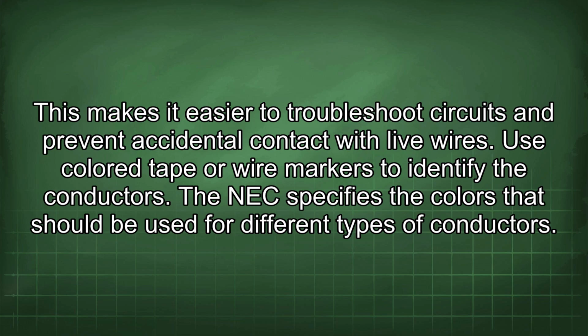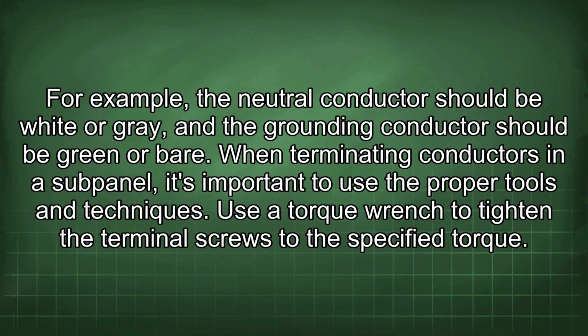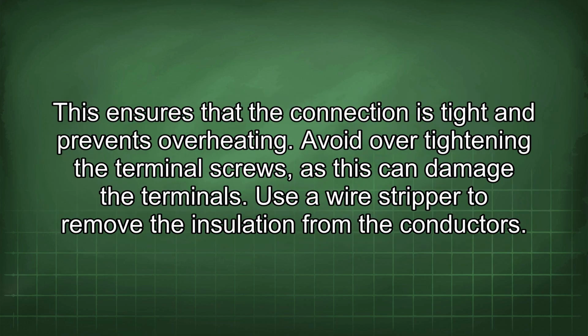Use color tape or wire markers to identify the conductors. The NEC specifies the colors that should be used for different types of conductors. For example, the neutral conductor should be white or gray, and the grounding conductor should be green or bare. When terminating conductors in a subpanel, it's important to use the proper tools and techniques. Use a torque wrench to tighten the terminal screws to the specified torque. This ensures that the connection is tight and prevents overheating. Avoid over-tightening the terminal screws, as this can damage the terminals.